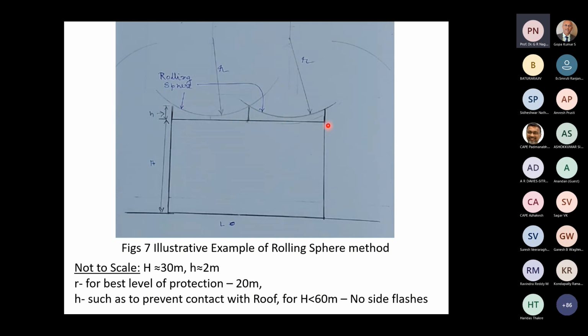Similarly, between the next corner, I need one more rod here. So the rolling sphere takes on this position. Therefore, when the sphere is rolled on the surface, it will not touch the surface at all, but it will contact only the tips of the rods, the lightning rods or the Franklin rods. That's the basic principle of the rolling sphere technique. This is not to scale, but the principle is very important.